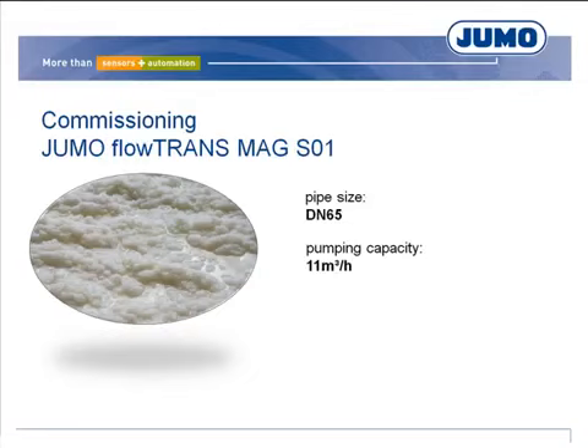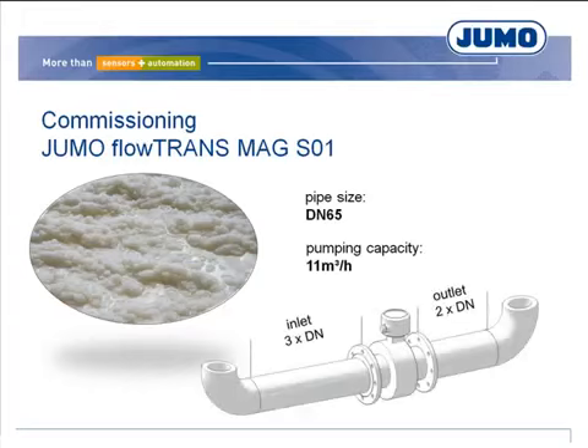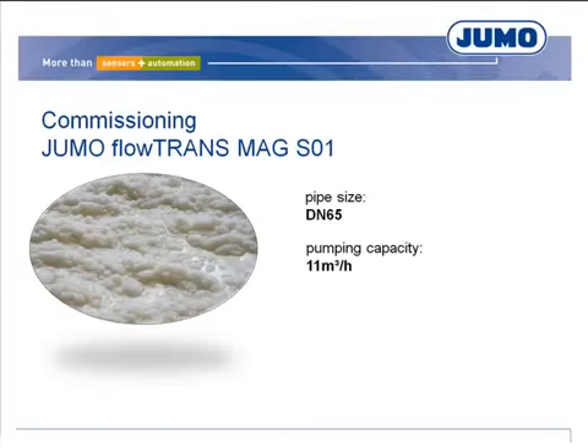This inlet and outlet section varies depending on the measuring method and can be up to 50 times the nominal pipe diameter in the worst case. For the flowTRANS MAG, an inlet section of 3 DN and an outlet section of 2 DN is generally sufficient, since the magnetic inductive method always recognizes the full pipe cross-section and thus is less sensitive to inhomogeneities in the flow profile.